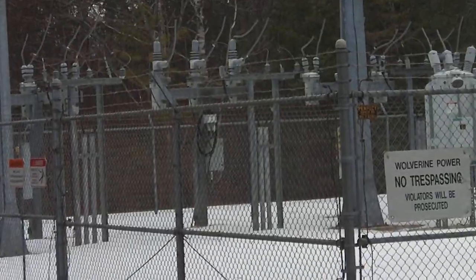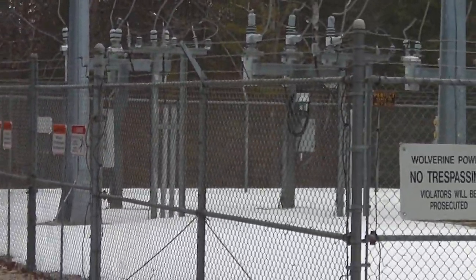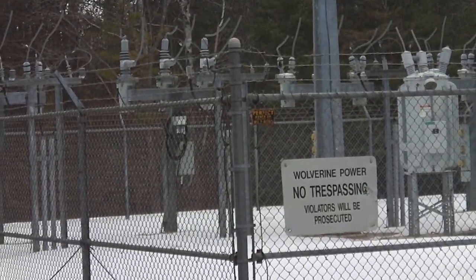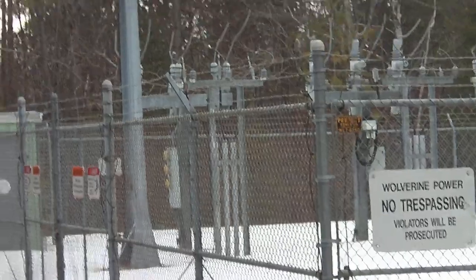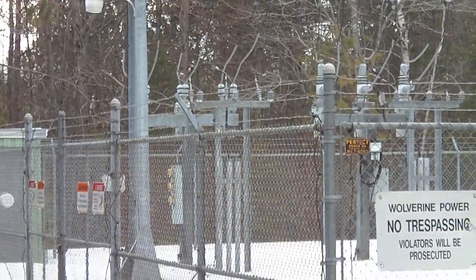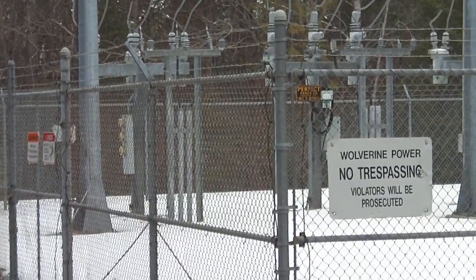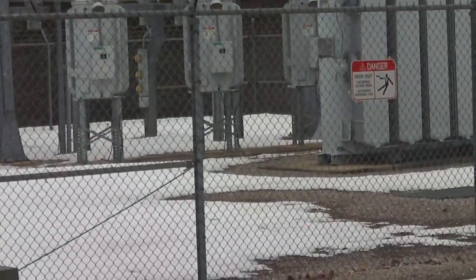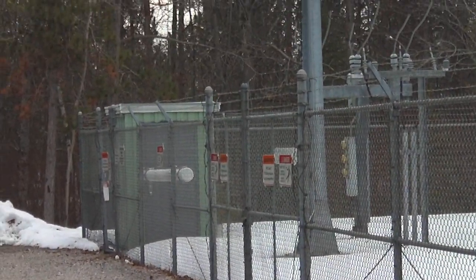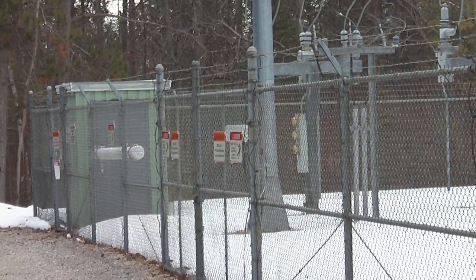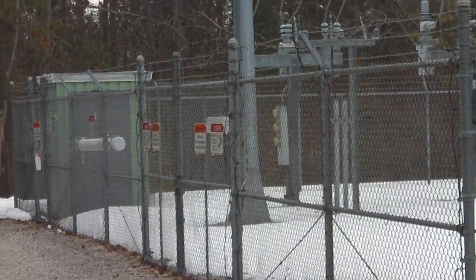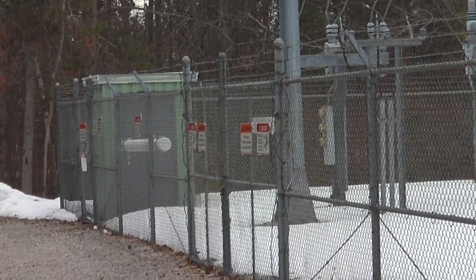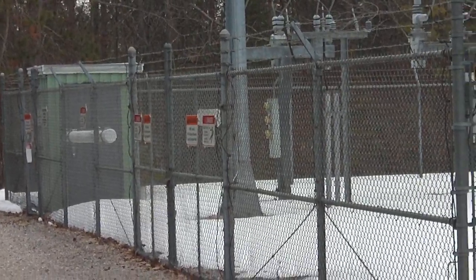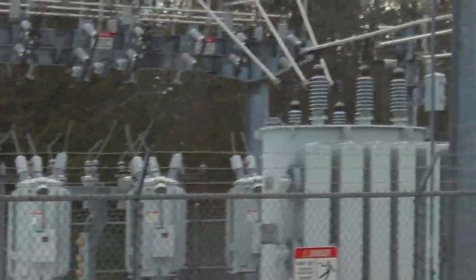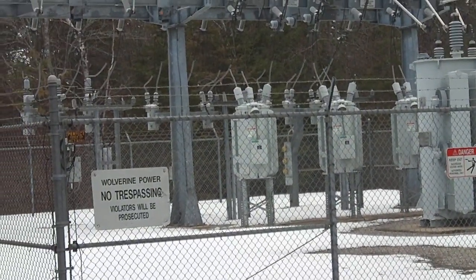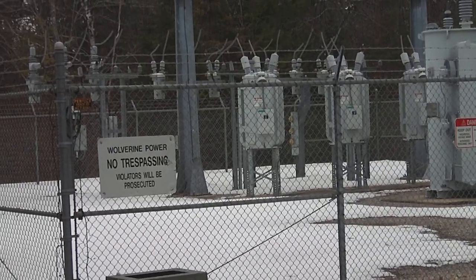If you look very carefully in the back, you will see some regulator meters up there. You can probably see it right next to this column holding up all that steel superstructure. You'll see those three vertical meters. There's another set identical to that down on the other end as well. And you will see the shack house here. For upgrade purposes, if they ever do some automation in here, this would house all of the protective relays that would be controlling the circuit breakers, which we don't have in this substation. We just have the high side fuses, and then of course reclosers protecting the distribution circuits coming out of the substation.